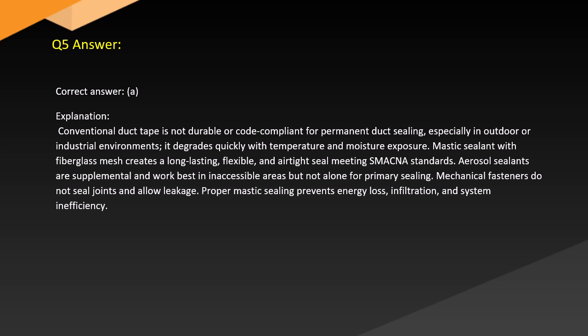Mastic sealant with fiberglass mesh creates the long-lasting, flexible, and airtight seal meeting SMACNA standards. Aerosol sealants are supplemental and work best in inaccessible areas, but not alone for primary sealing. Mechanical fasteners do not seal joints and allow leakage. Proper mastic sealing prevents energy loss, infiltration, and system inefficiency.